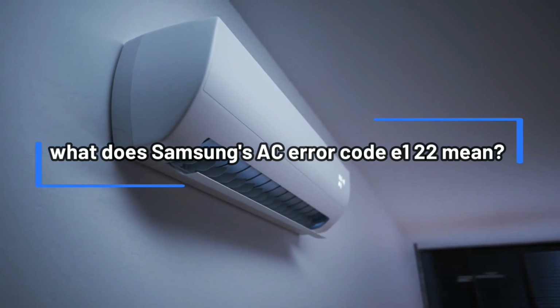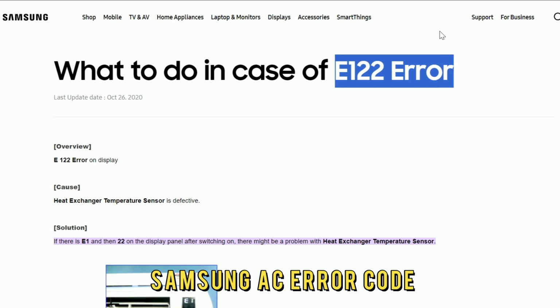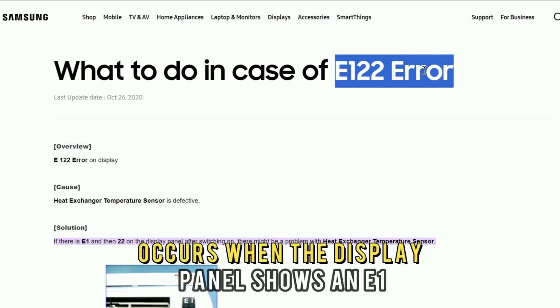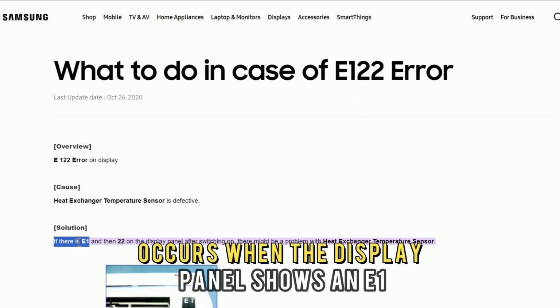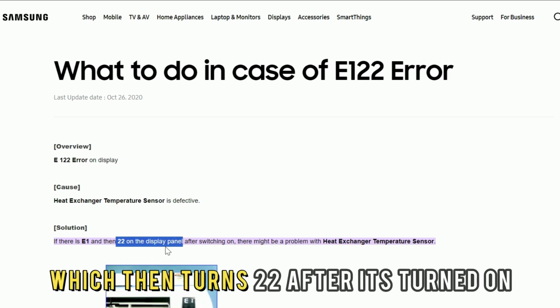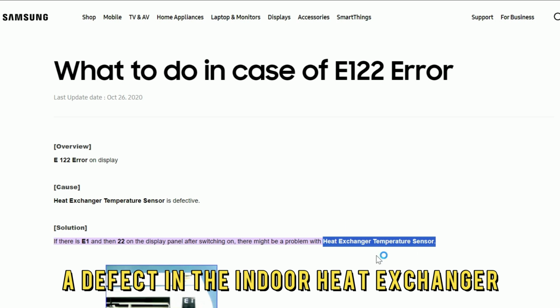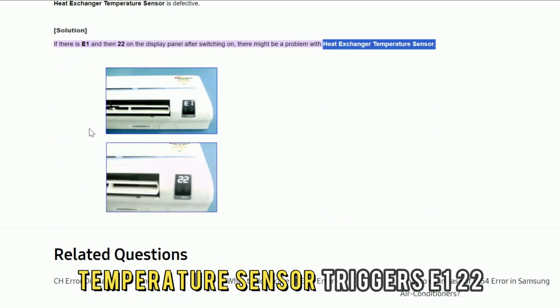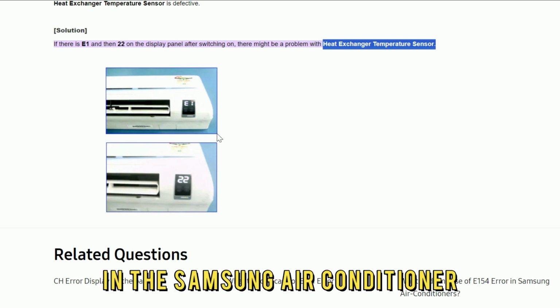What does Samsung's AC error code E122 mean? It occurs when the display panel shows E1, which then turns to 22 after it's turned on. A defect in the indoor heat exchanger temperature sensor triggers the E122 error in the Samsung air conditioner.